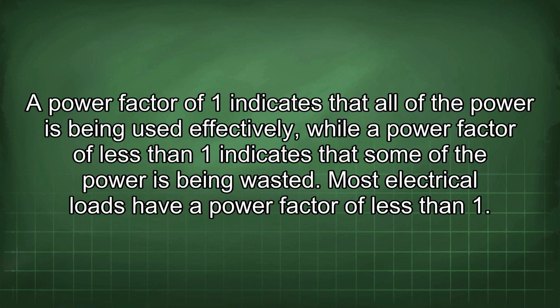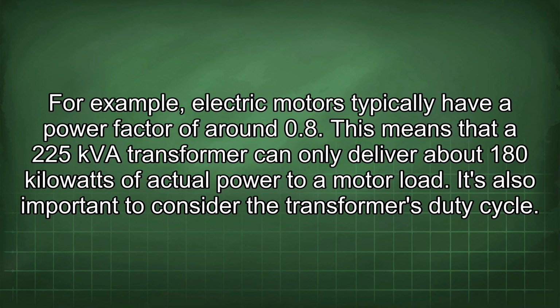Most electrical loads have a power factor of less than 1. For example, electric motors typically have a power factor of around 0.8. This means that a 225 kVA transformer can only deliver about 180 kilowatts of actual power to a motor load.